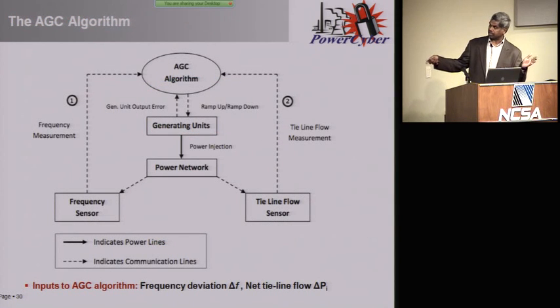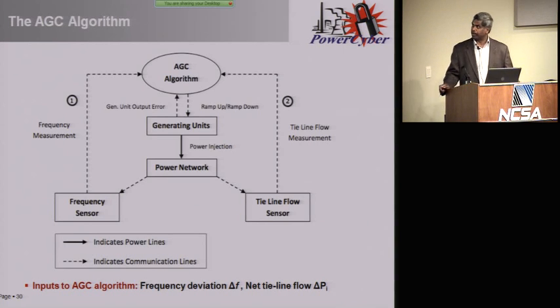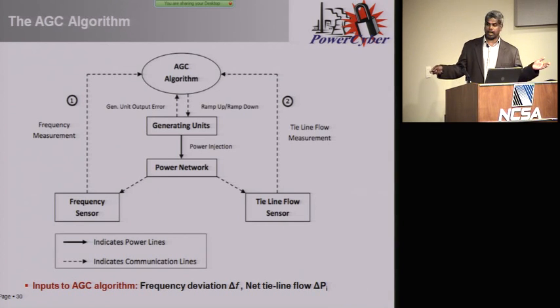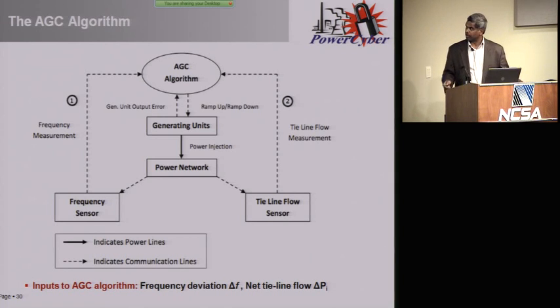This is the AGC algorithm. As I said, the AGC algorithm takes tie line power flow and frequency as measurement inputs. It computes what is known as the area control error. Based on the area control error, it determines whether to ramp up or ramp down the generation associated with that particular control area, and how much generation increase or decrease needs to be performed. Those actions are then physically applied on the power grid. In this flow chart, the dotted arrows represent cyber-related communication, while the others represent actual physical actions happening in the power system. So we are talking about somebody disrupting or modifying this tie line measurement or frequency measurement through a data integrity attack.